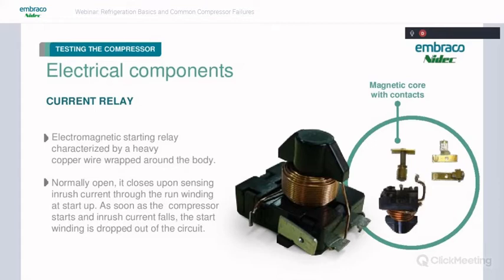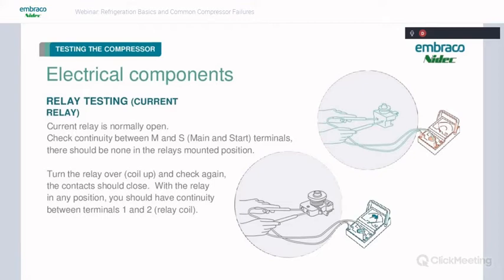But basically, if we find one of these and we want to test it, you can pull it off the compressor, and being that it's normally open, you can test the run and the start terminals that plug onto the compressor. In the mounted position, there should be no continuity. If there is, the contacts could be stuck. Then turn the relay over and check it again. Gravity should cause the contacts to close, and you should have continuity. And then if you test the coil on terminals 1 and 2, you should have continuity. If not, you've got an open or damaged coil.